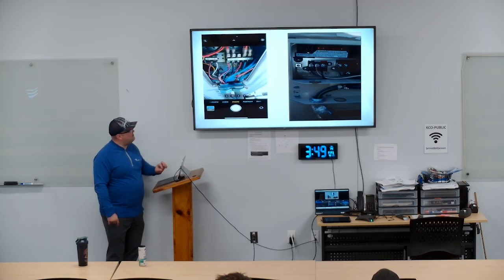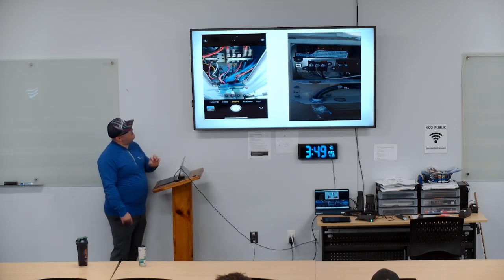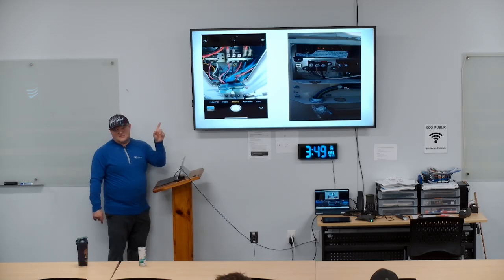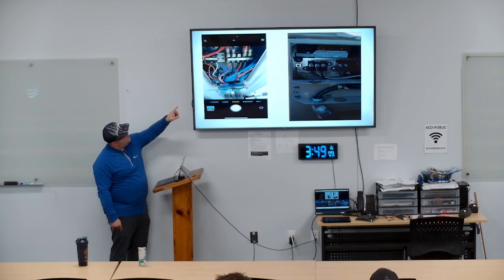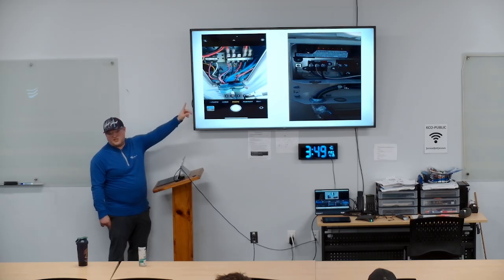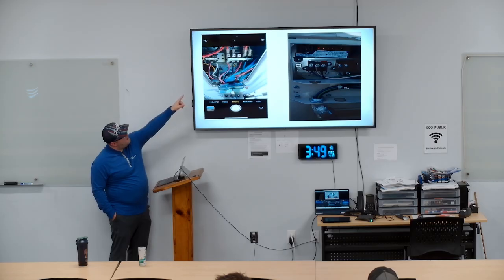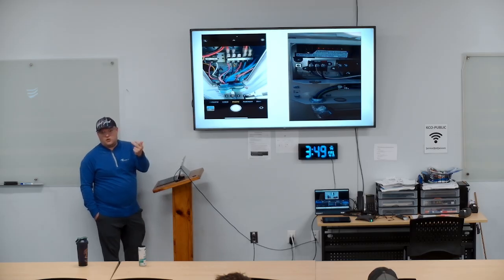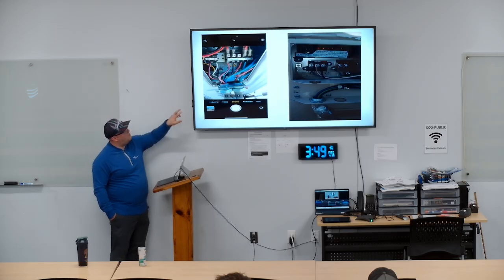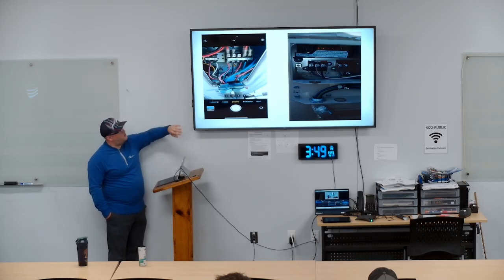The left picture. I know it's a little hard to see. It was the one that I had. So this is an example of one with a communication. So L1, L2 by themselves on the far side is where the electrician came in. L1, L2 and ground. The 1 L1 and the 2 L2, that's coming off there and going back into the indoor unit to power. So that's the power to the indoor. S1 and S2 are just communication. So that's where I've been telling people, pull them both. Now on this job, the electrician did it all.